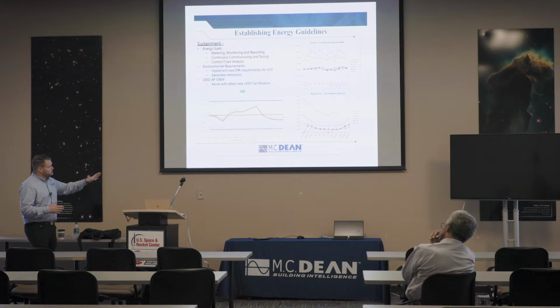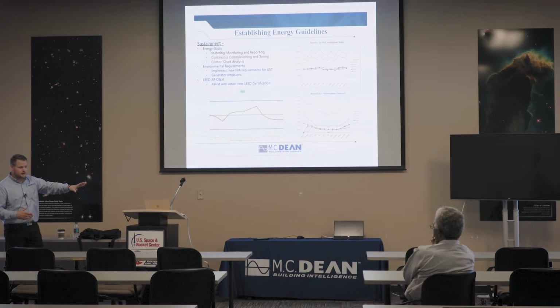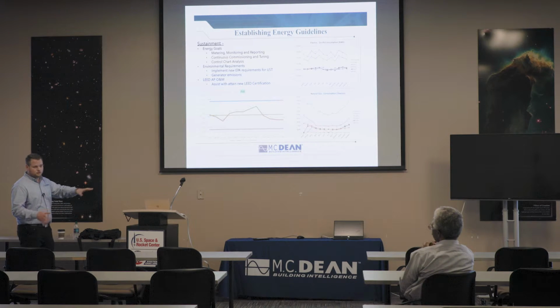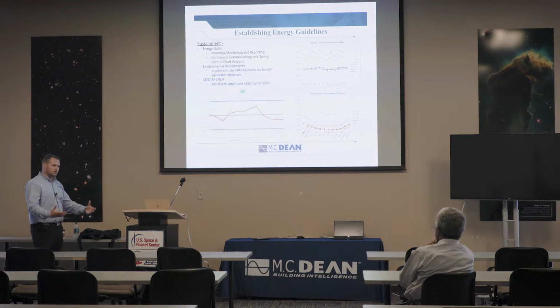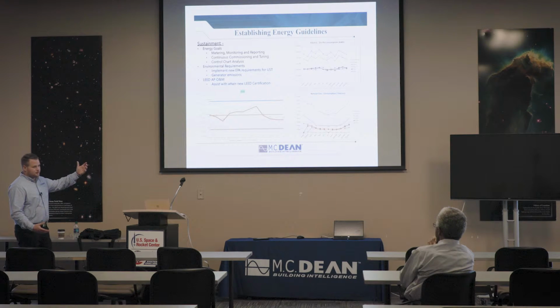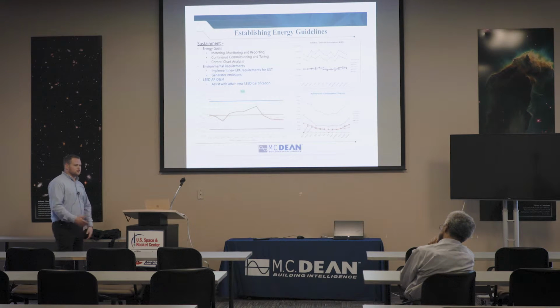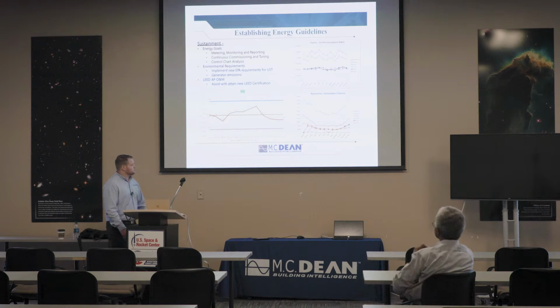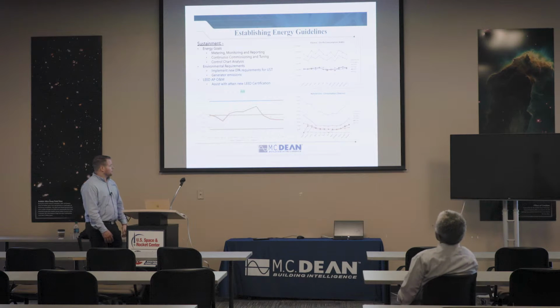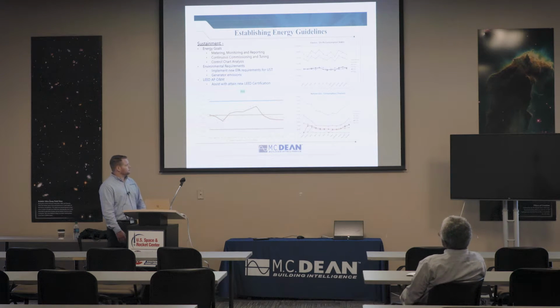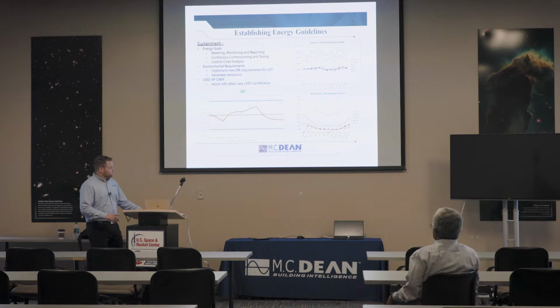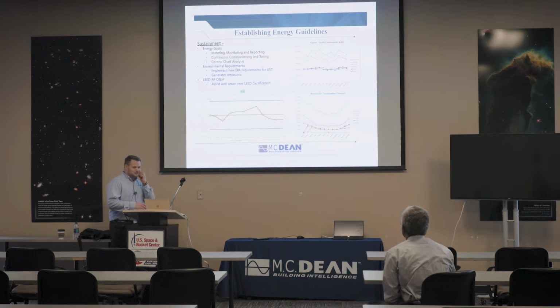But you can see here, we trended up and started dipping down. The reason behind that is during the summer months, we run our cooling towers more, we run our chillers more, there's a lot more cooling demand. So we see our energy requirement go up. And then once we get into the later months, when we get free cooling from outside, we can dip back down. So for a 300,000 square foot data center, our current PUE being 1.46 is pretty good for a data center that size.